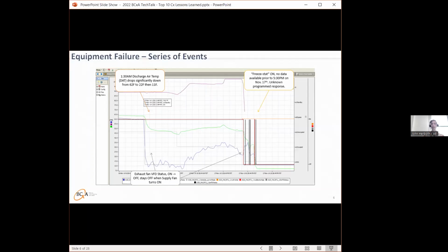And when you have a heat recovery unit with a heat wheel and your exhaust fan stops working, guess what? You don't transfer any of that building heat to that incoming cold outside air, and your supply air temperature drops. With the software freeze stat not working and shutting down the unit, now you have cold air coming over the coil. And then I'm pretty sure it was early in the morning and the heating water system wasn't hot enough, or there wasn't enough demand, or there wasn't hot enough water to keep those coils from freezing up.